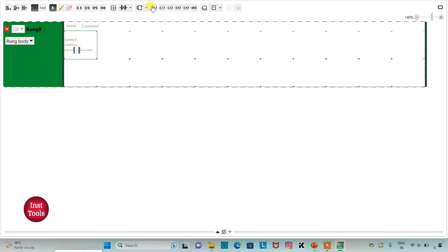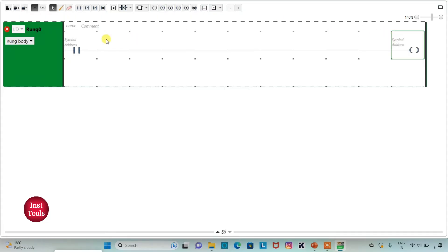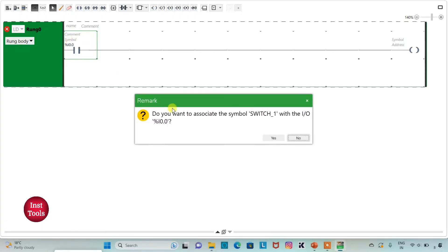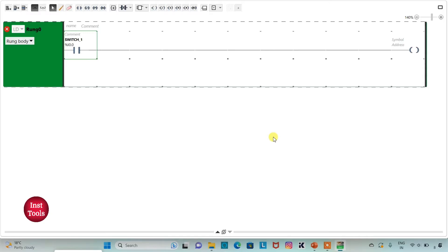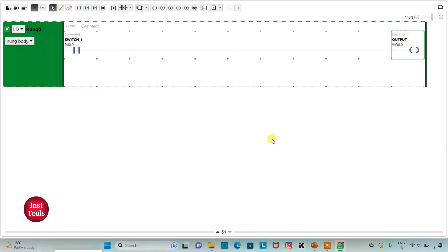I will insert a coil, then assign the address to the contact as I0.0 and add the symbol switch1. Then I will assign the address to the coil as Q0.0 and add the symbol output. So when switch1 is turned on, output will be on, and when switch1 is turned off, output will be off.